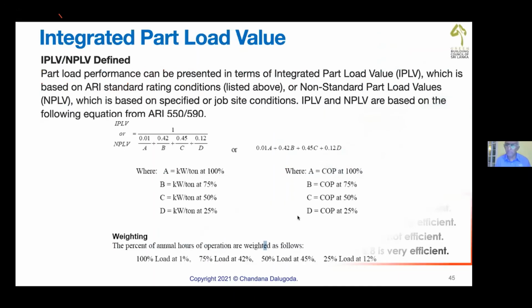Another problem with HVAC systems for buildings is that the cooling load is not constant throughout the day. It varies through the day because the heat transfer varies. Heat generation is varying throughout the day. So if you select equipment giving very good efficiency at full load, that may not be the case in actual operation. The building behaves on a part load, more operational on a part load.